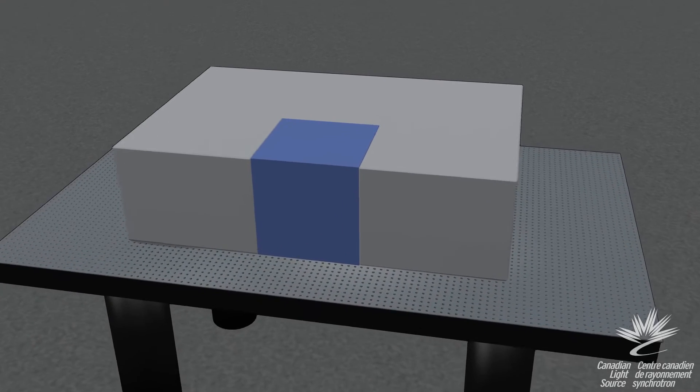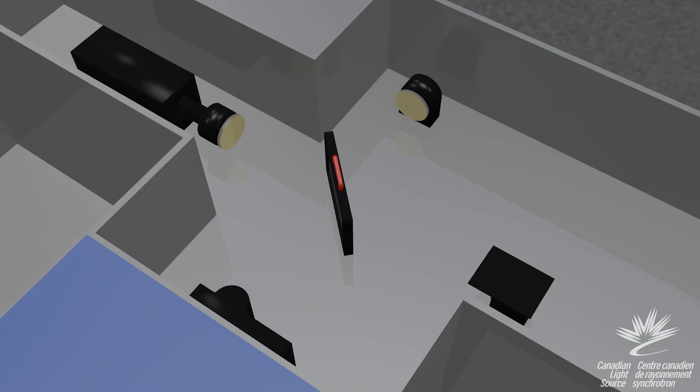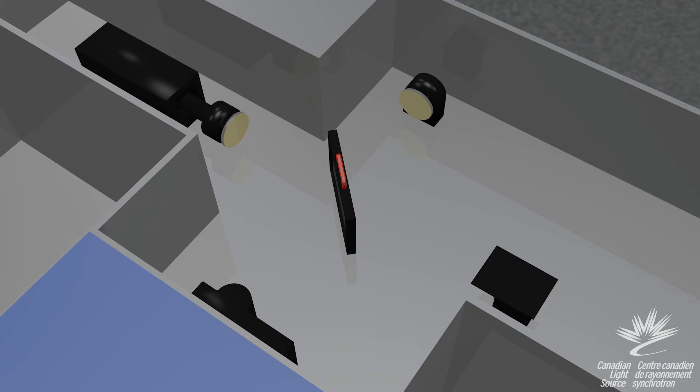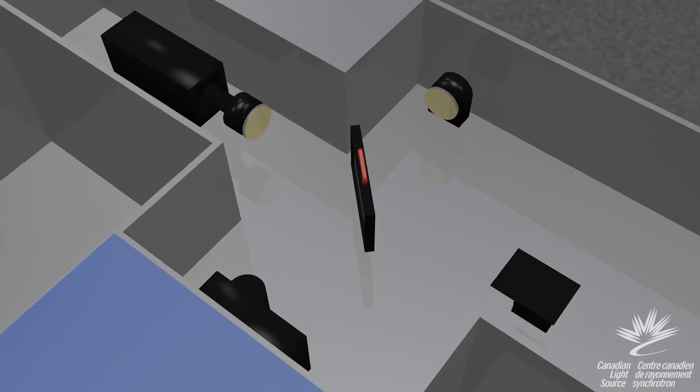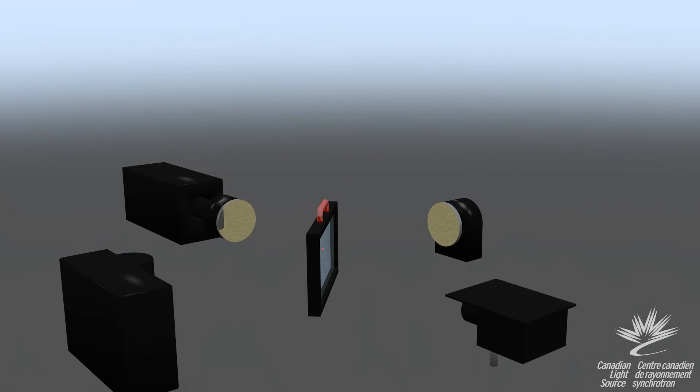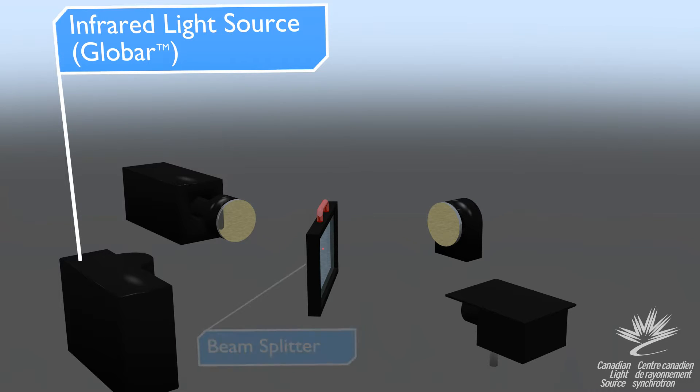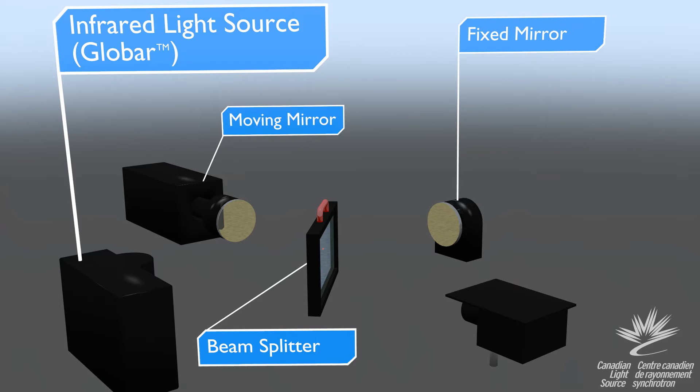You may be familiar with the original Michelson interferometer. It is a simple optical system used to create interfered light at certain wavelengths. The interferometer consists of five essential components: the IR light source, the beam splitter, two mirrors—one fixed and one that can be moved—and a detector.